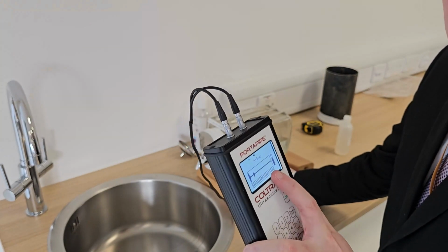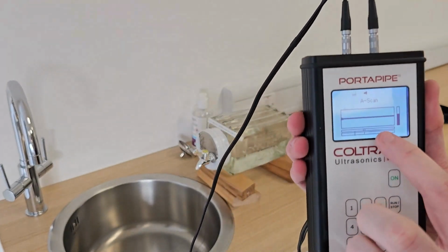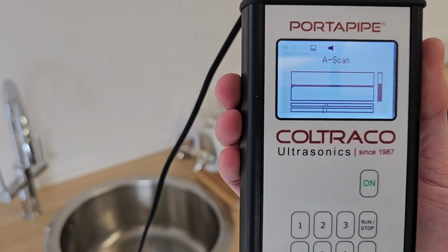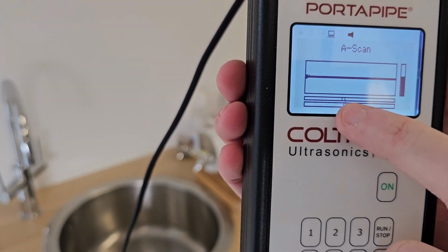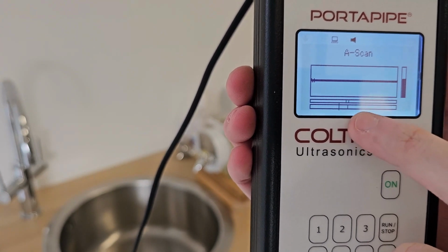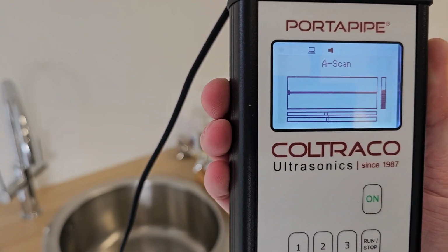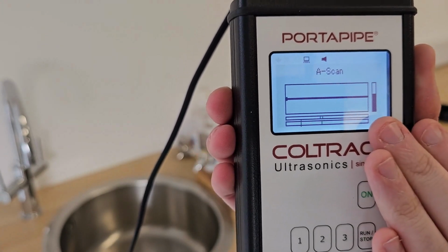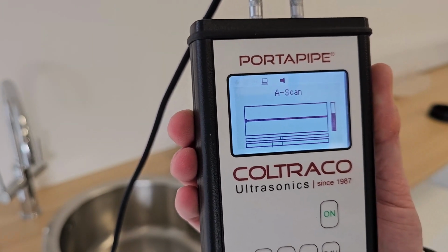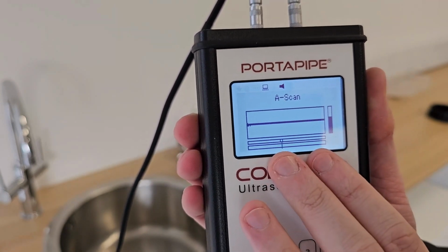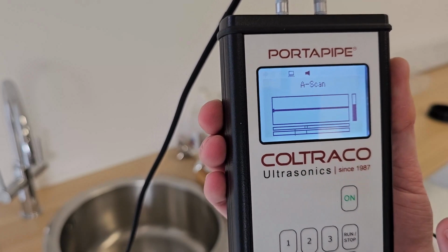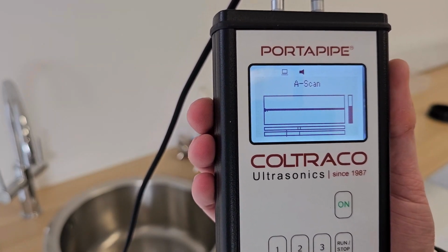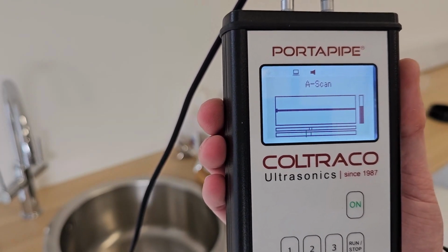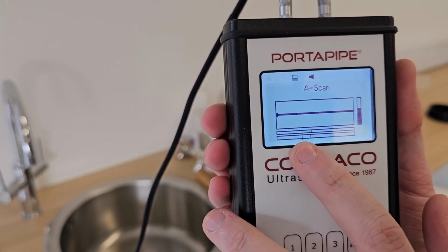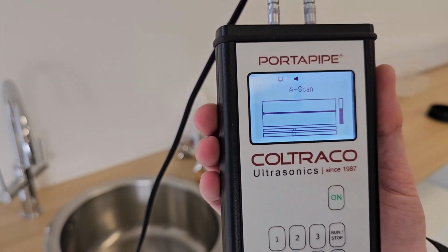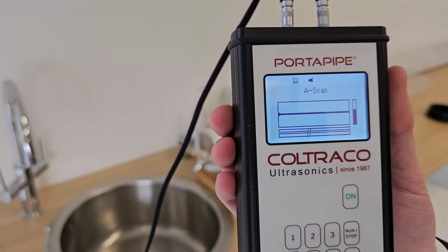If we compare this, I'll take it off for a moment, we have these couple of bars below our graph. The top one has got 2 lines, and the bottom one has got 1 line that moves around and 1 line that is fixed. The fixed line in our bottom bar indicates the exact position of the theoretical liquid level response time, and the top bar indicates a range of acceptable values based on minor errors in the time of flight measurements. The moving bar locks onto whatever peak or reflection it detects that it thinks is the liquid level.